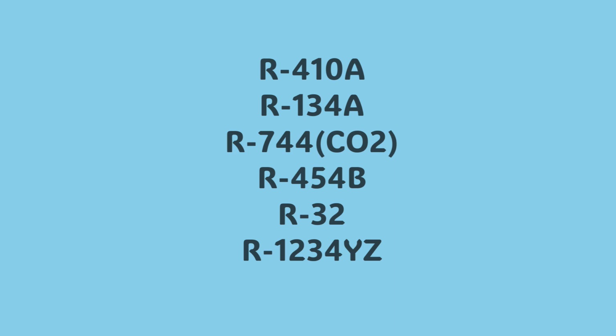When designing central heat pump water heating systems, the choice of refrigerant is critical. It affects the temperatures the system can deliver, how it performs in different climates, and even the environmental impact of the installation. Let's look at the three most common refrigerants used in HPWH systems today: R134A, R410A, and R744, also known as CO2.